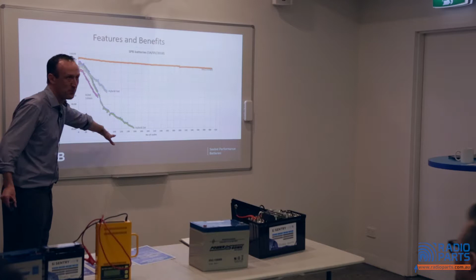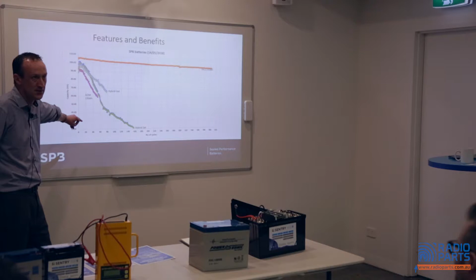This is pretty much 100% depth of discharge, but 100 cycles, 100% depth of discharge, it's only like 35 ampere hour left in the battery. That's the capacity of the battery after 100 cycles, down to 100% depth of discharge. You see what's happening here? The degradation in the capacity, the holding capacity of the battery is absolutely smashed the deeper you go down.